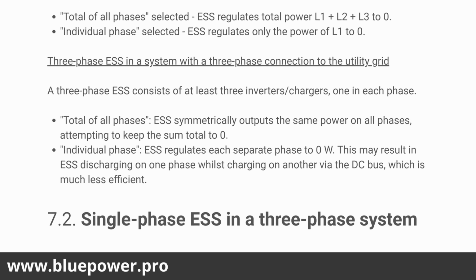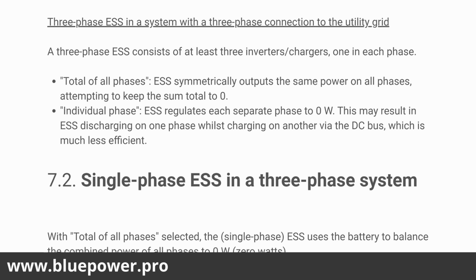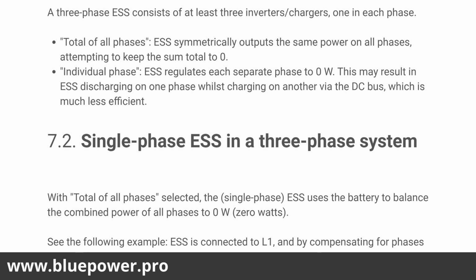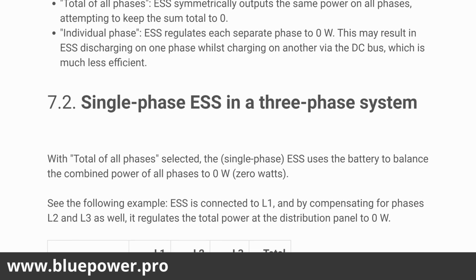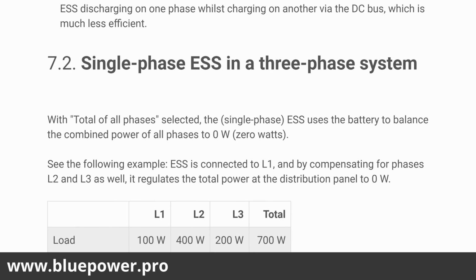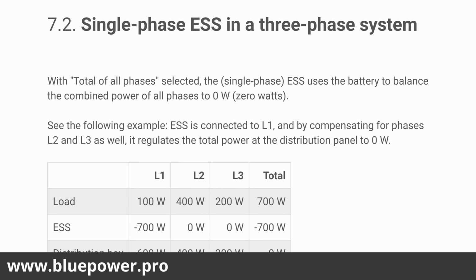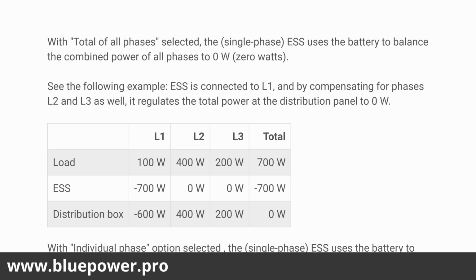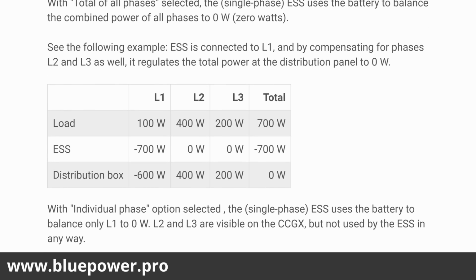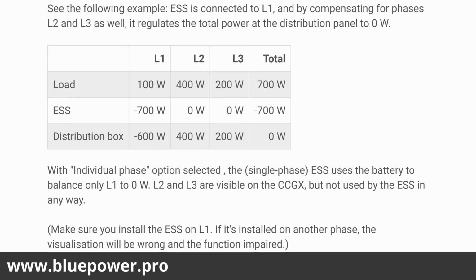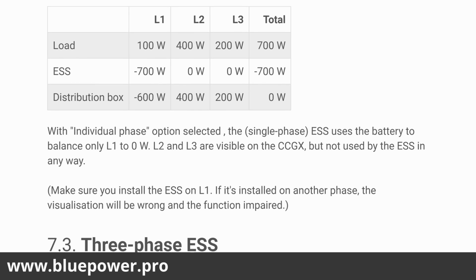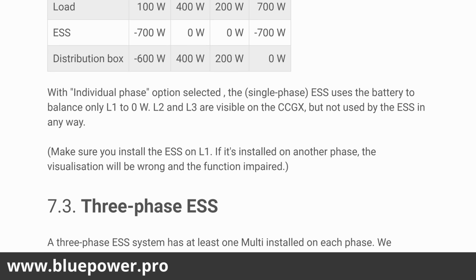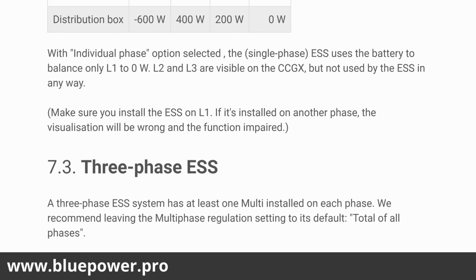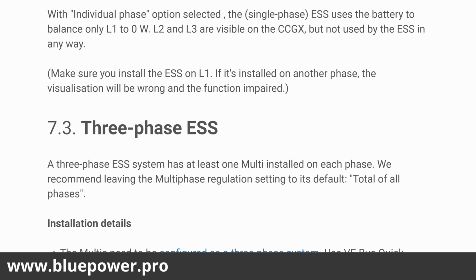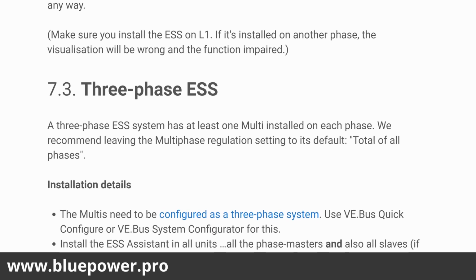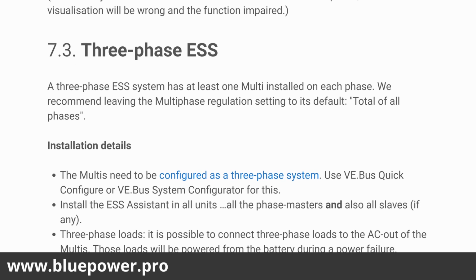If you've got the total of all phases selected, it is going to calculate the maximum or the total consumption over the 3 phases, and that's not going to exceed your grid set point. But what that does is, if you've got unbalanced AC loads, it will allow feed-in from the DC bus from one inverter into the grid, and then you draw that power that you feed into the grid on another phase. So the total consumption of the meter will then still be 0 watts, for instance, but it's going to reverse feed 1 kilowatt on the 3rd phase and draw it on the 2nd phase to feed the higher load on the 2nd phase, for instance.